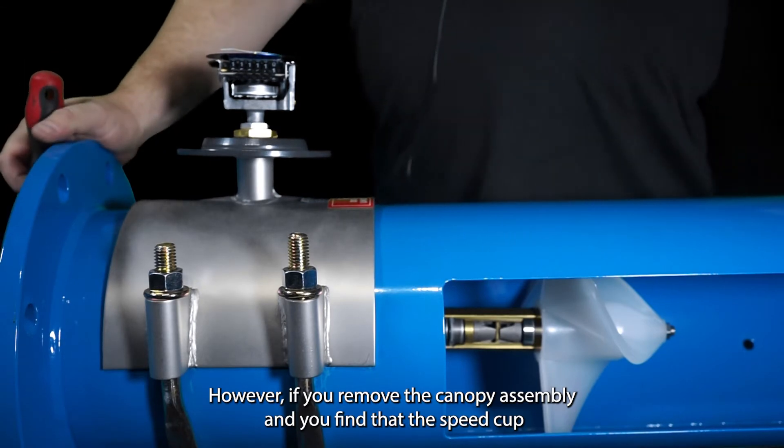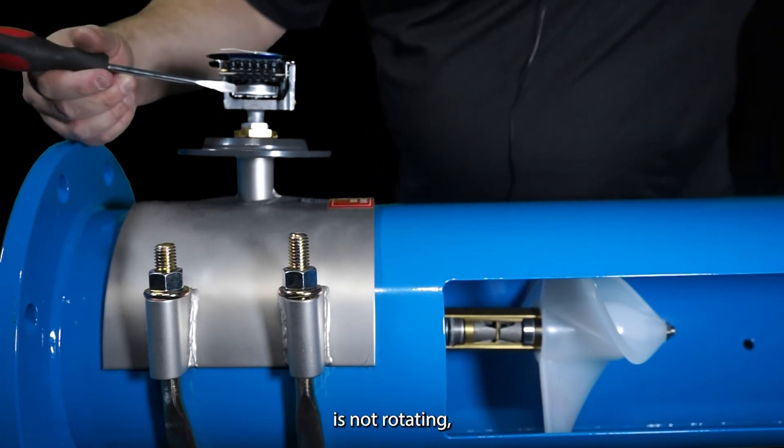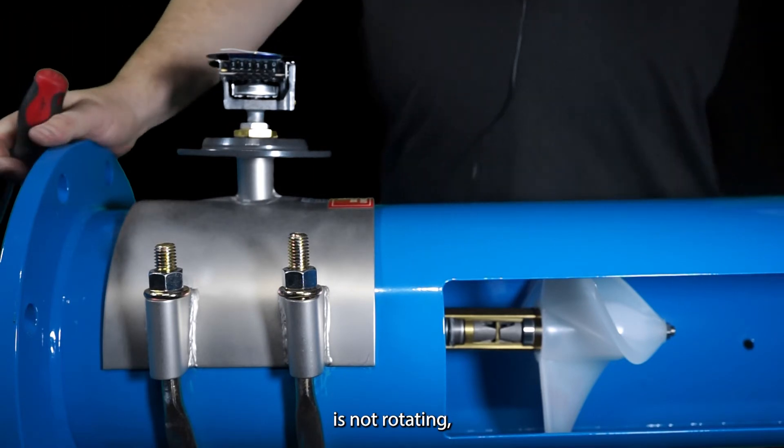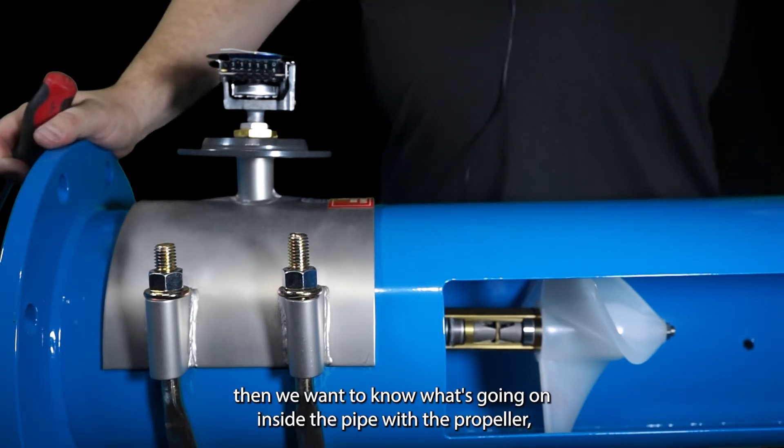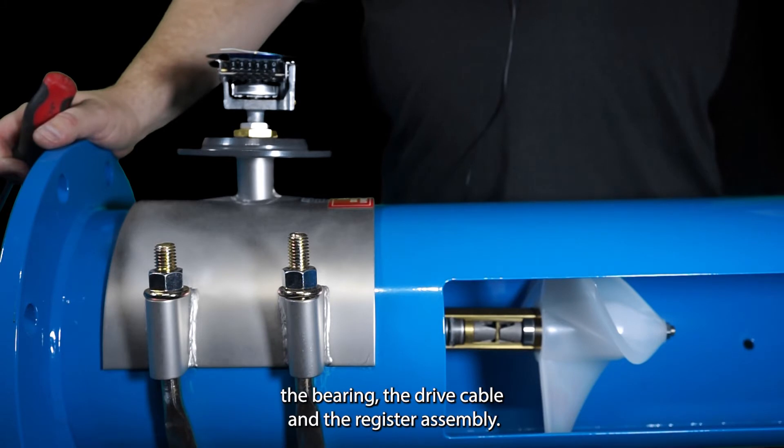However if you remove the canopy assembly and you find that the speed cup is not rotating then we want to know what's going on inside the pipe with the propeller, the bearing, the drive cable, and the register assembly.